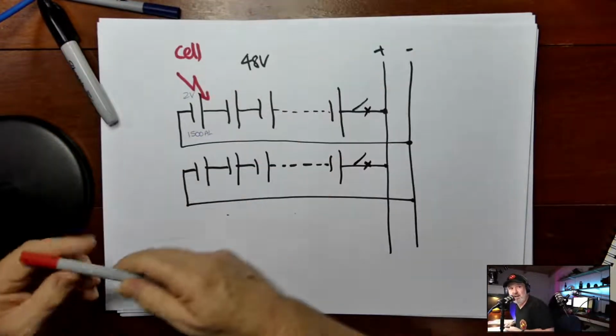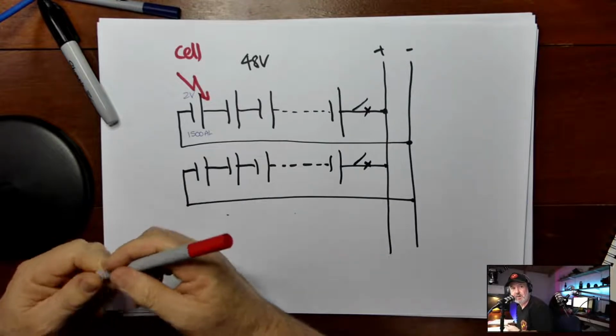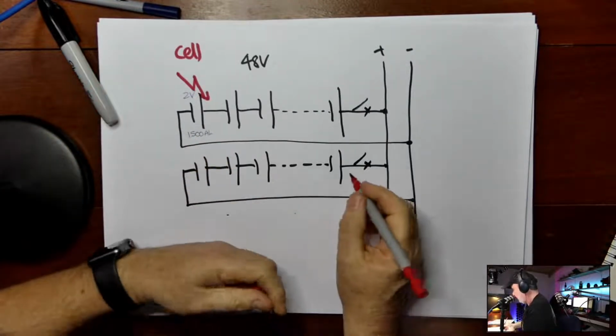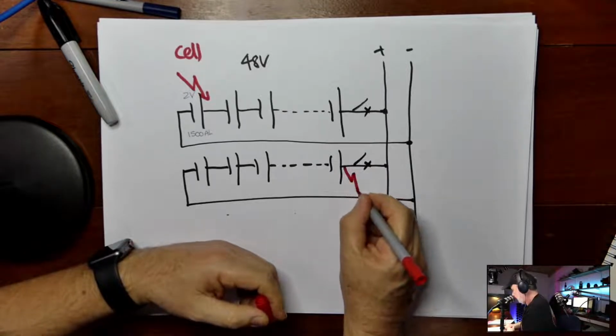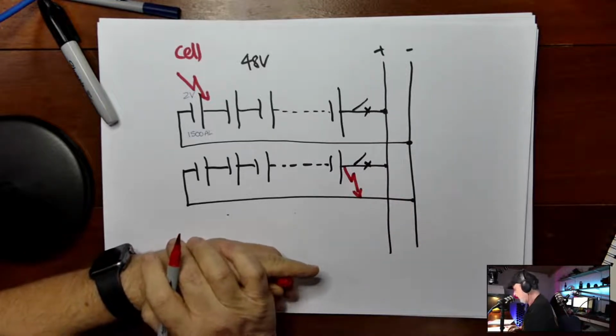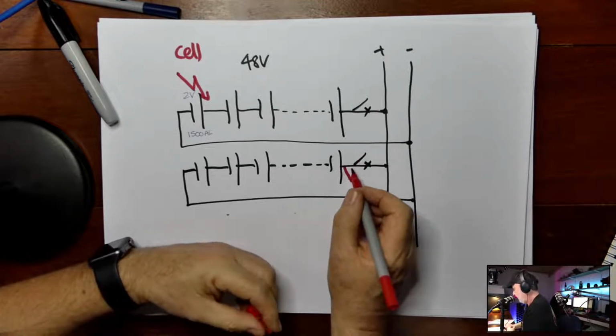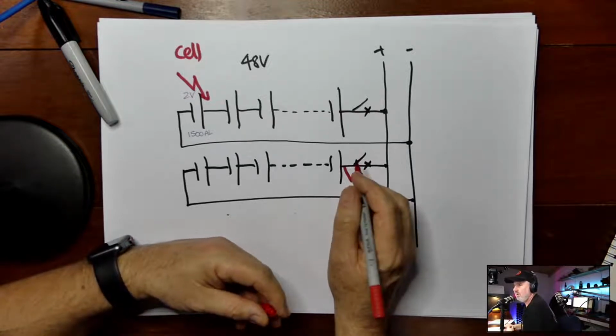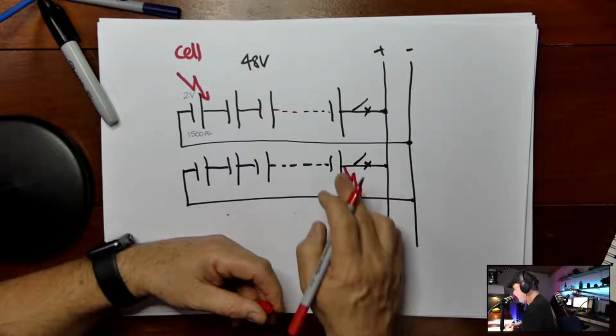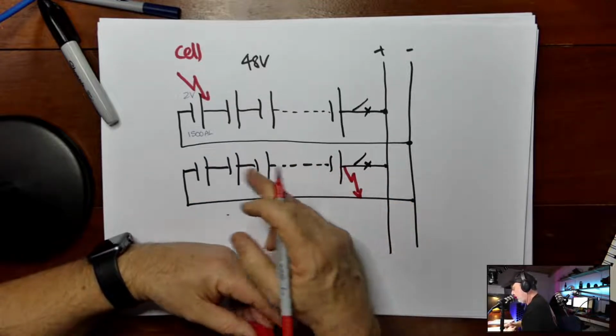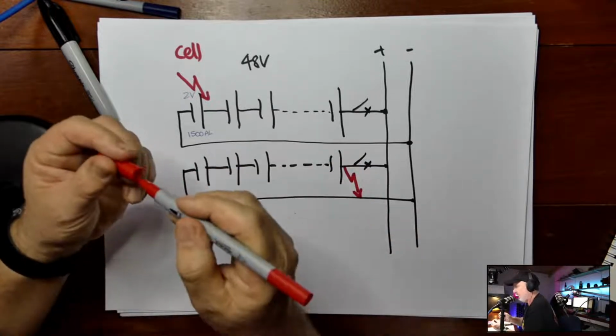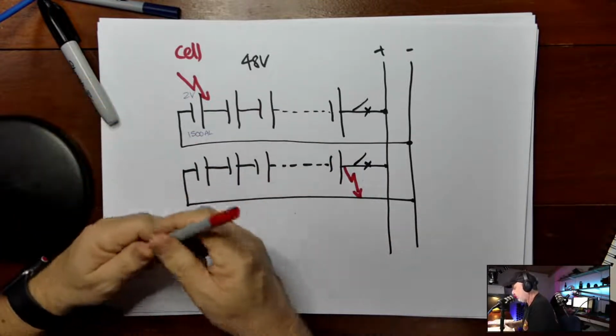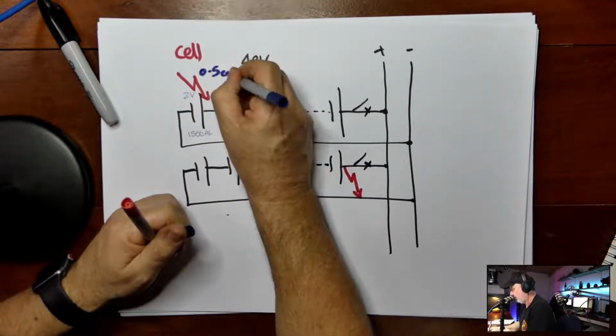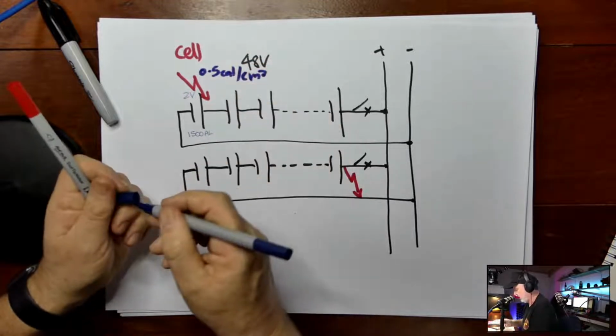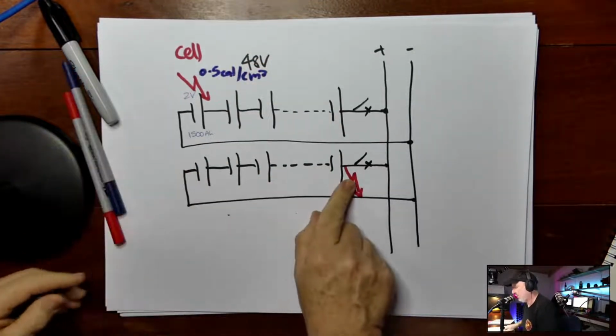So let's introduce a new fault condition here. When you're installing that string overcurrent protection, you accidentally could short circuit at this point here. So now, on the battery side of the string overcurrent protection, you have put a spanner across the terminals, and you've now got 48 volts instead of 2 volts, and you've got 16,882 amps. So I should write what the cals were. I think it was 0.5 cal here. So that was pretty low. Let's have a look what it is over here.